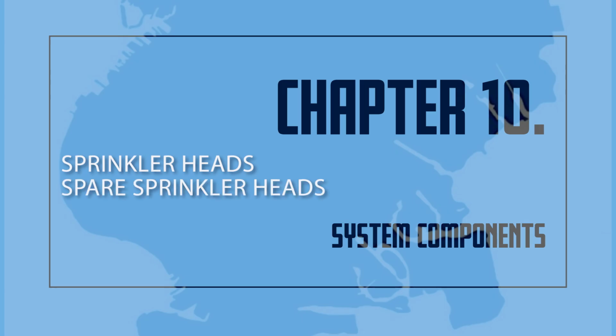Spare sprinkler heads. Sprinklers required for emergency replacement must be representative of the type of sprinklers installed along with the proper wrenches. These wrenches shall be provided in the spare head cabinet. It is critical sprinklers be replaced with devices that will perform similarly to the original system sprinklers. Sprinklers that are replaced during an emergency by unlicensed individuals require that the devices used have been verified appropriate for the protected area by a master fire suppression piping contractor.